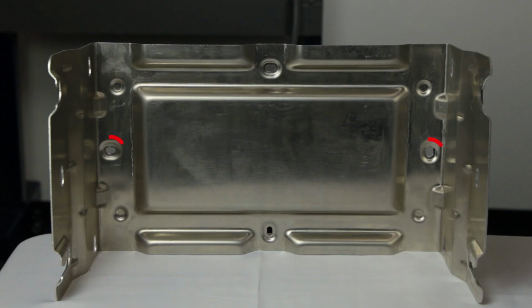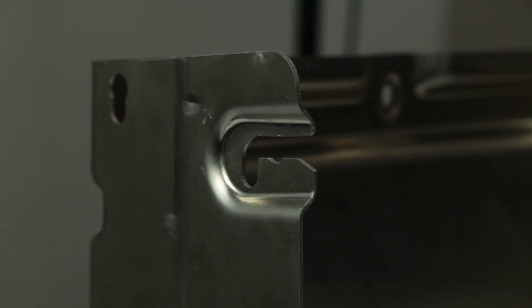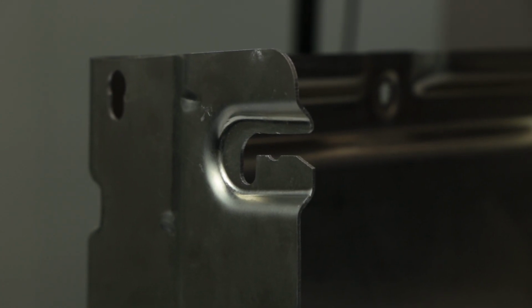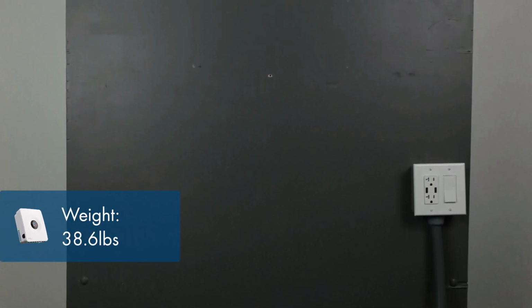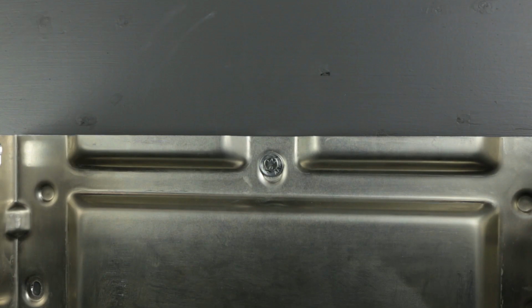Preferably, install the bracket with two screws across two studs. Alternatively, you can use two screws on a single stud. Install the bracket with the hook slots facing downwards. Choose a flat surface to support the weight of the inverter. Insert a washer onto each screw and tighten them with a socket wrench.